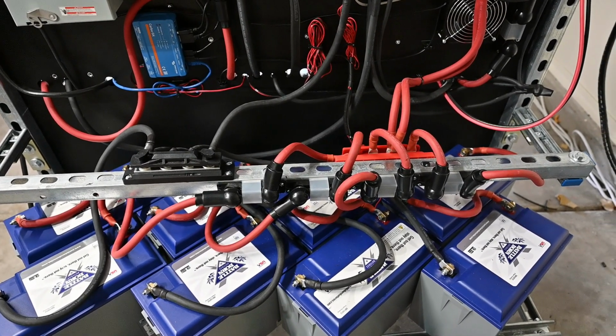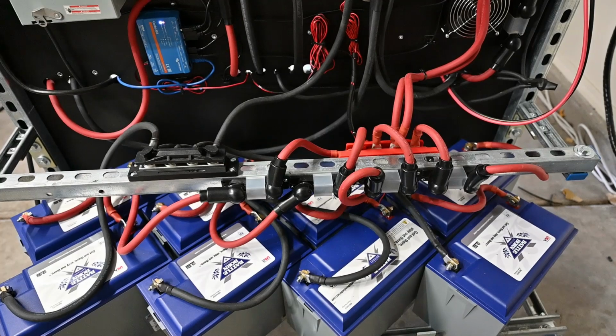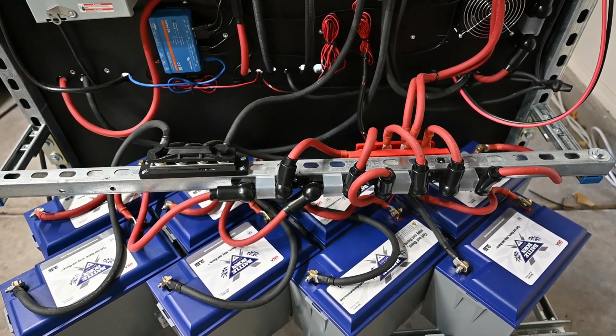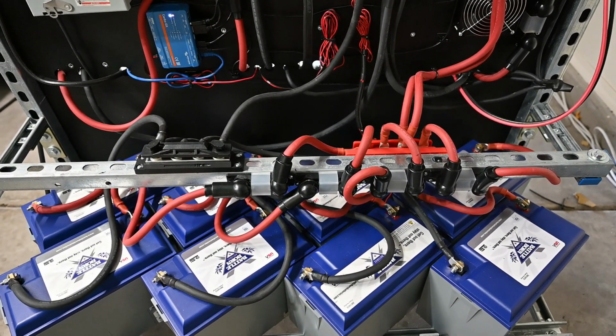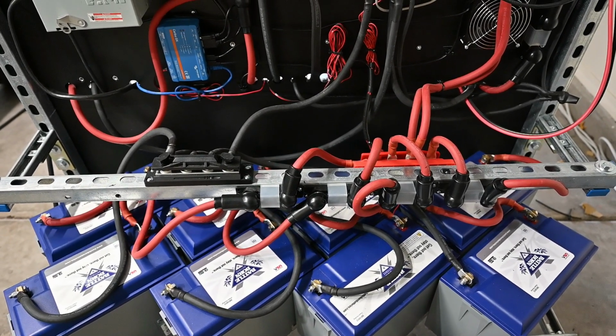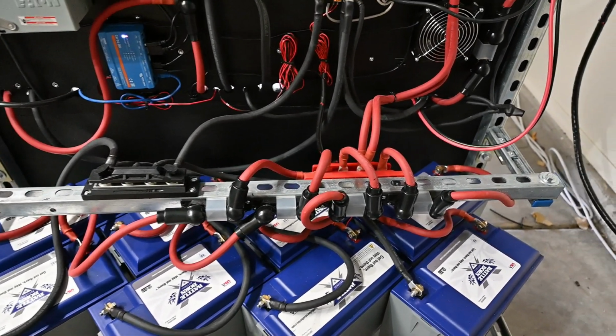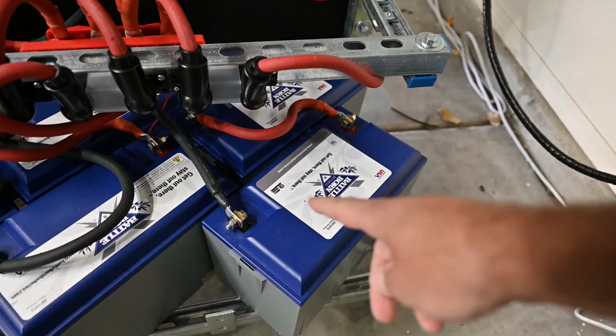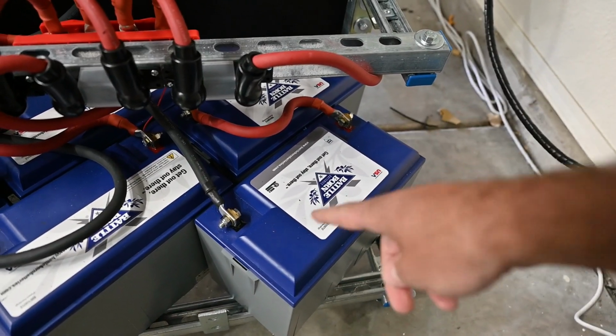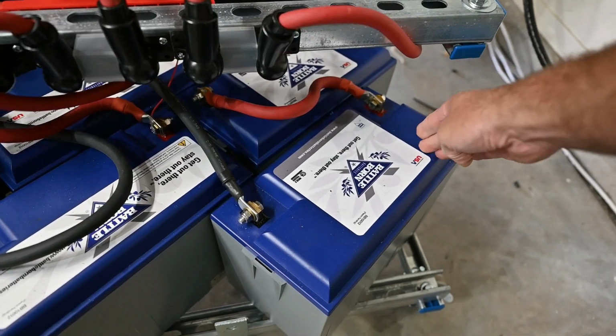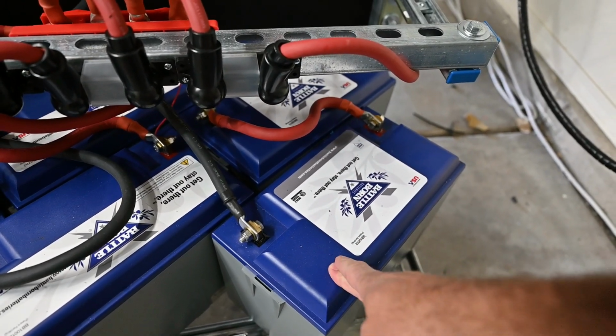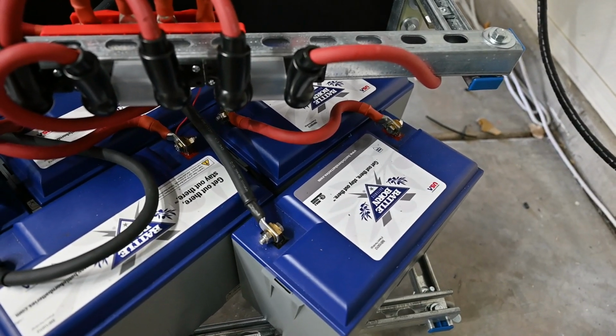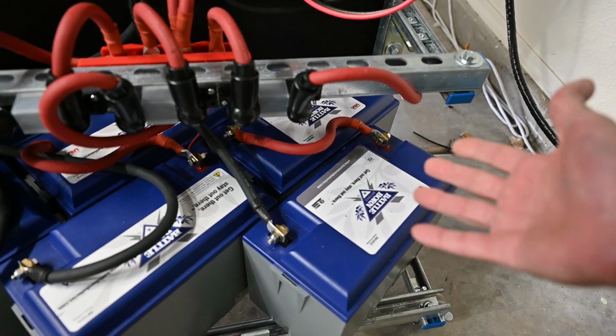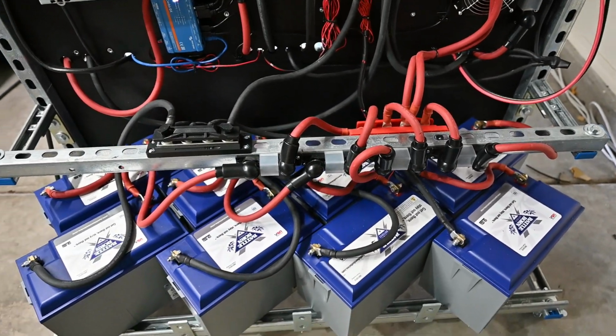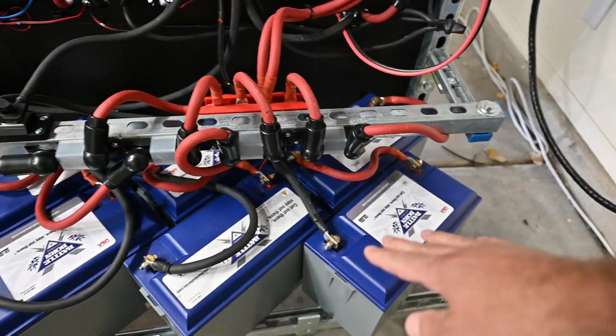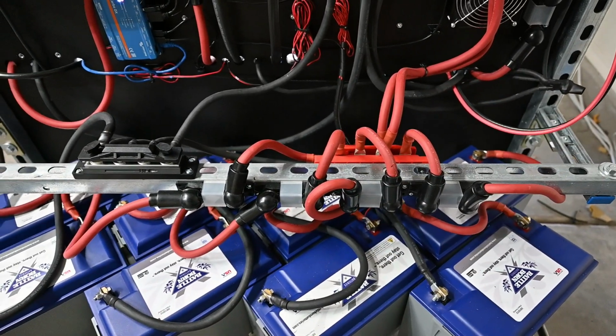Once a certain voltage is achieved, the batteries are held at an absorption phase of, in this case, 28.8 volts. Once higher than 14 volts is achieved across the battery, the 4 individual cells inside equalize their voltage. It's said to try to bring your system up to 100% charge at least once a week, so all the individual cells in all the batteries can normalize their voltage.